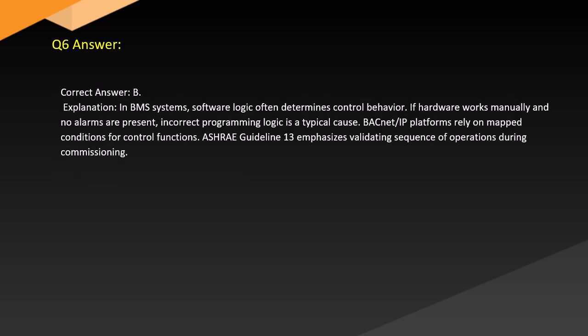Answer. Correct answer: B. Explanation. In BMS systems, software logic often determines control behavior. If hardware works manually and no alarms are present, incorrect programming logic is a typical cause. BACnet platforms rely on mapped conditions for control functions. ASHRAE Guideline 13 emphasizes validating sequence of operations during commissioning.